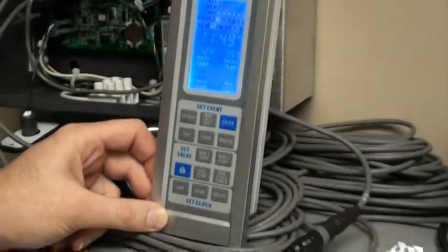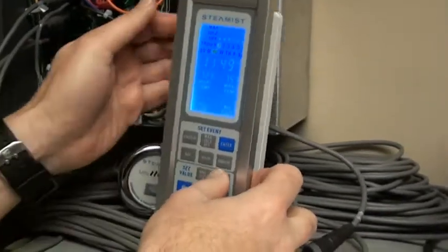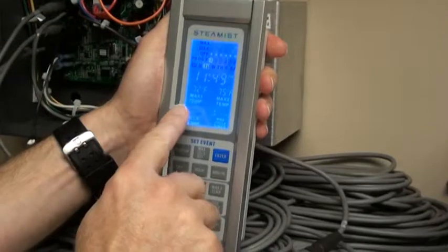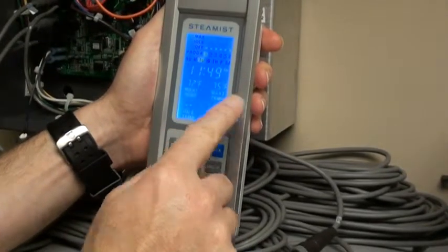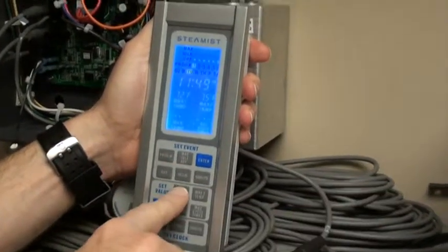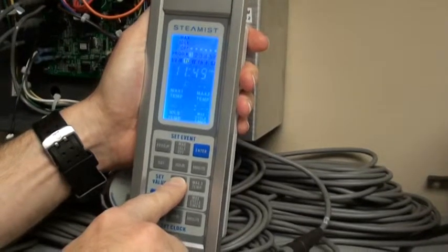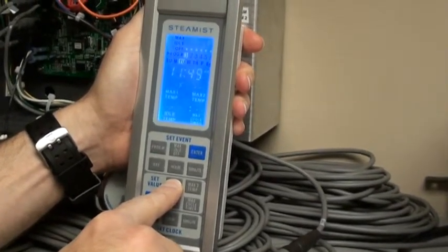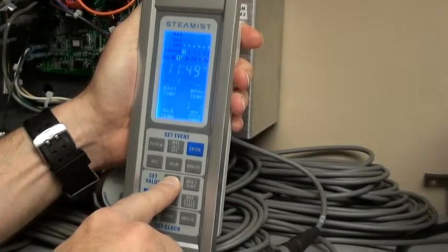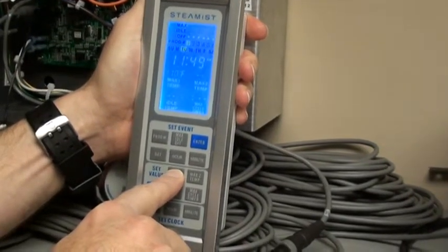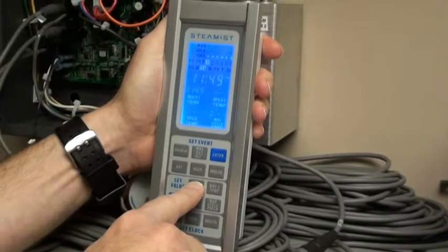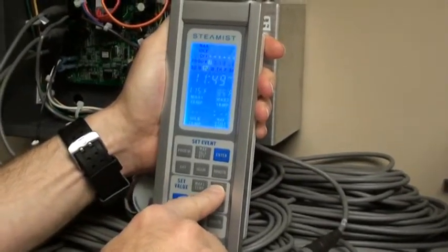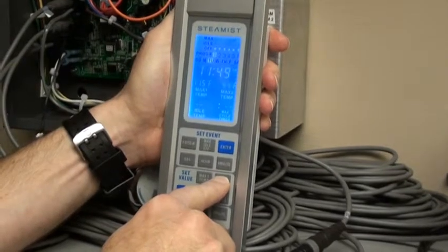So we will do that starting with max 1 temp. Right now it's showing us the ambient temperature in both rooms. Room 1 at 72 degrees, room 2 at 75 degrees. So max 1 temp, we push and hold it. We'll get it to 115 degrees. Max 2 temp, in this case, let's say it's the women's room, we'll set it to 110 degrees.